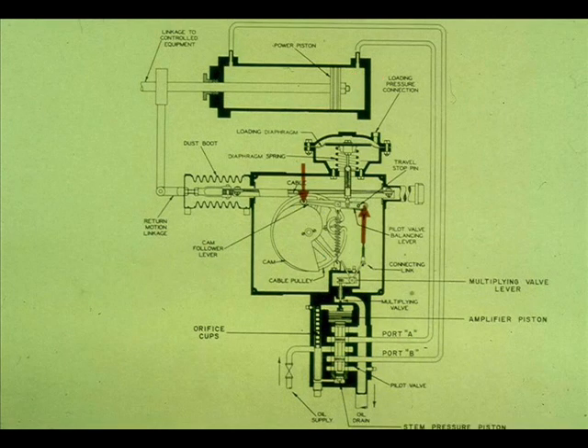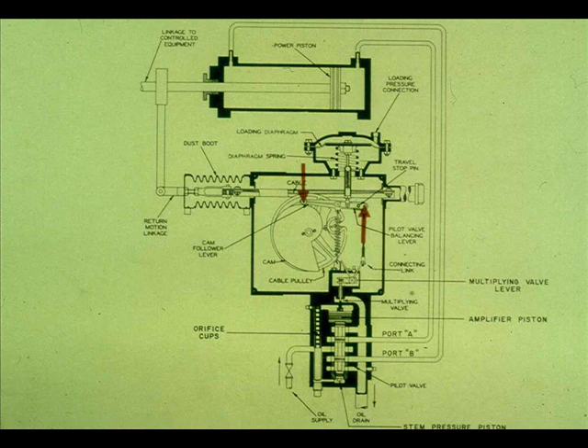The pilot valve balancing lever rotates. The left end lowers. The right end raises. This repositions the multiplying valve, which repositions the pilot valve. The system is rebalanced.